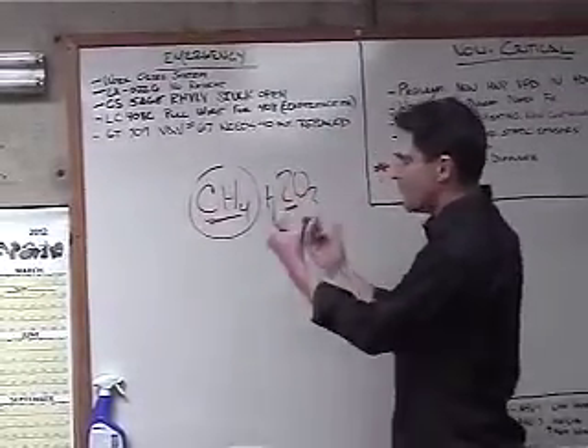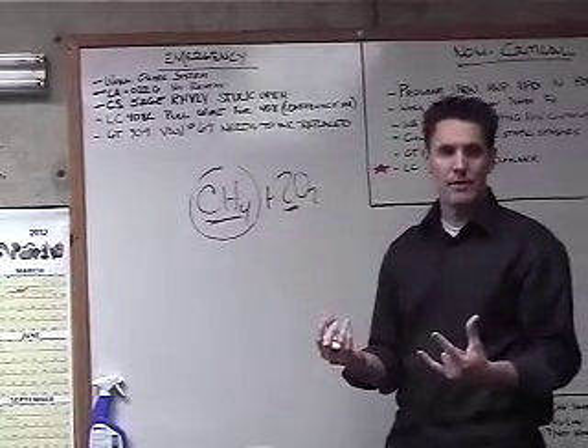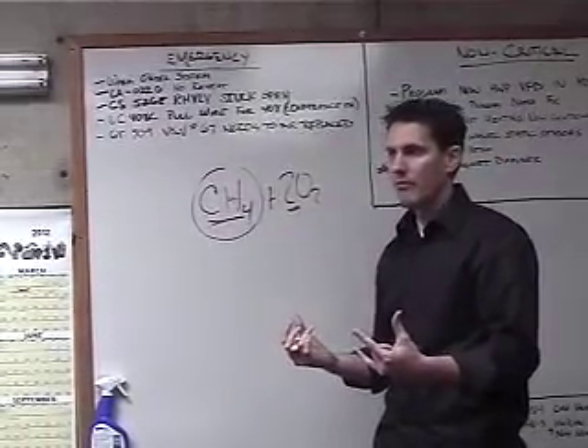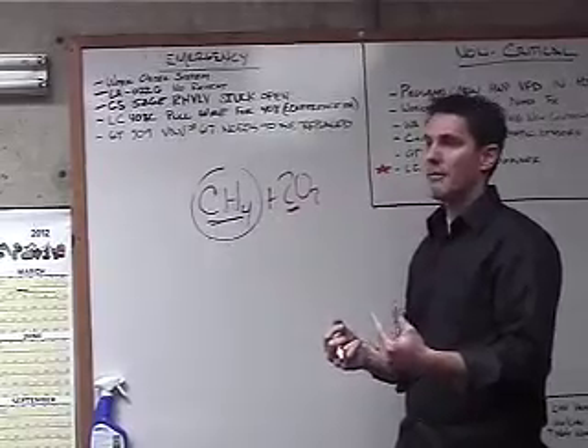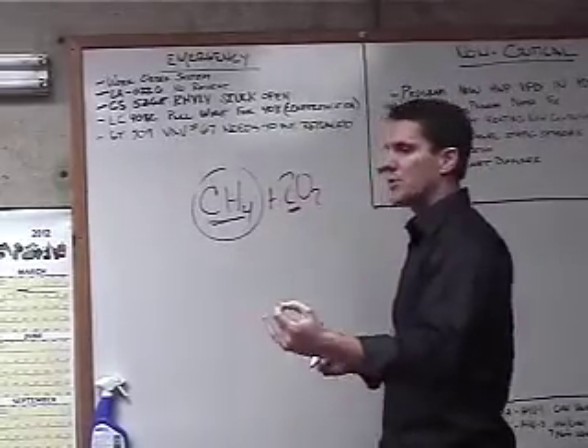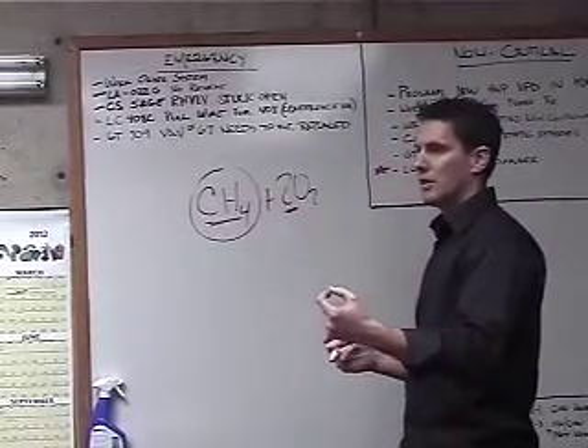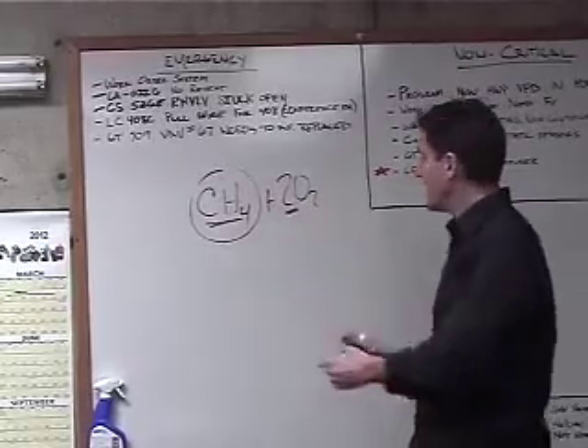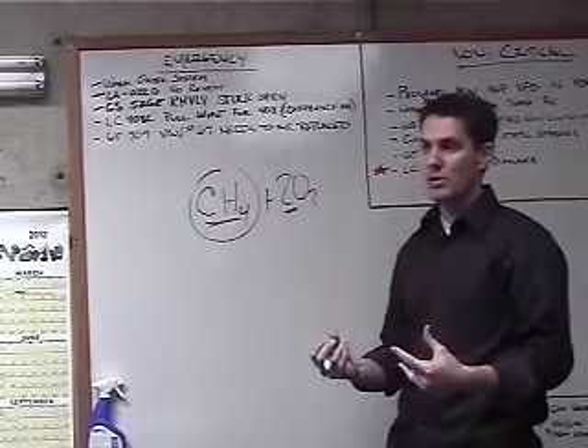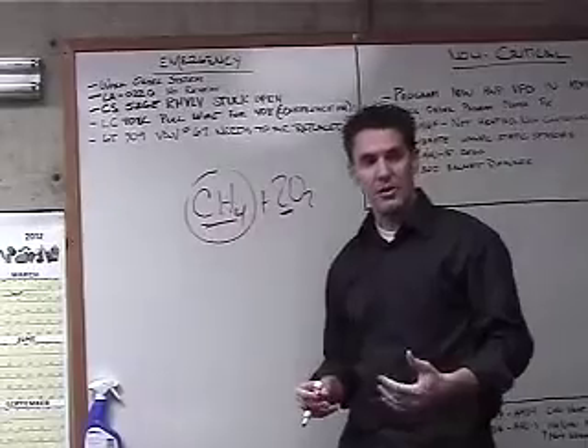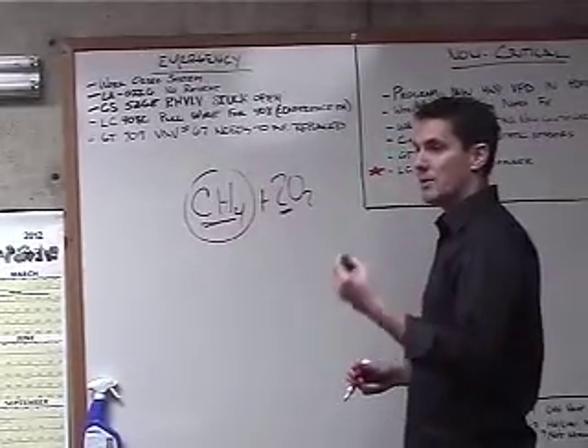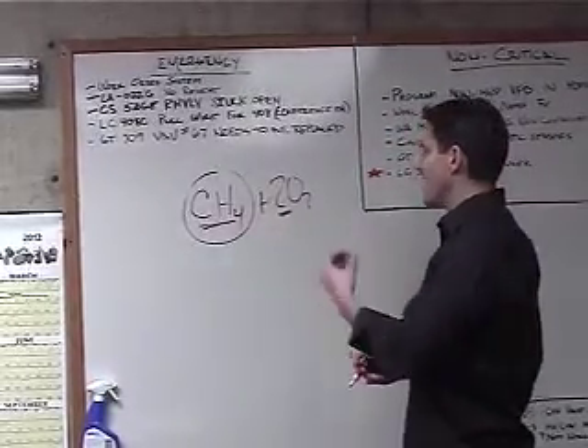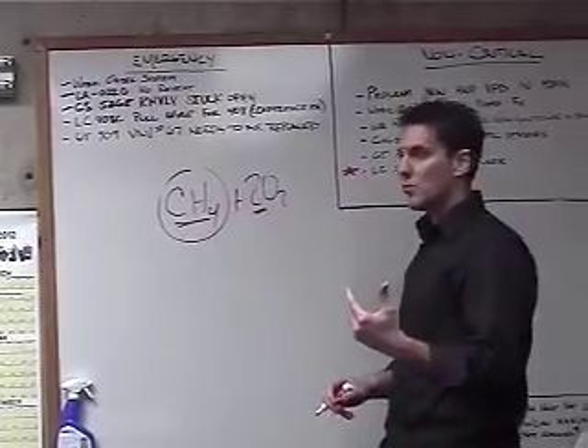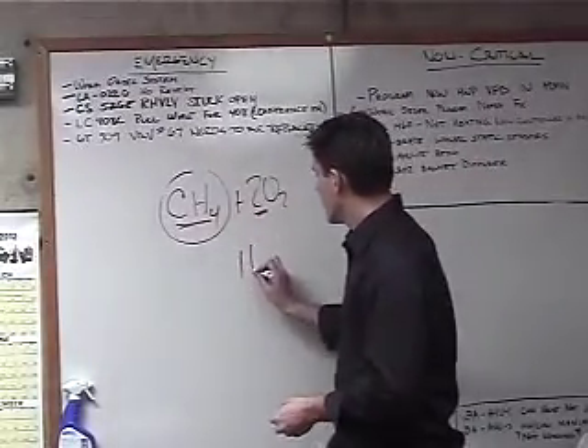If we get this mixture, do we automatically have combustion? No, I mean, we have this mixture going on all the time. What do we have to introduce in order to get combustion? Ignition. Some type of ignition source, right? We have to get this mixture up to its ignition temperature using a hot surface igniter, using a spark, something to get that up to its ignition temperature. Once we do, now we have combustion occurring. Combustion will give us heat. That's what we're trying for.